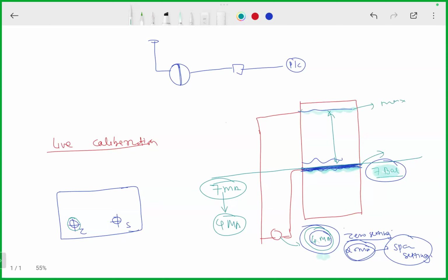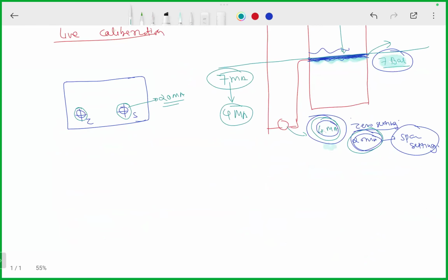So when water level is at the highest point, at that time the output signal should be 20 milliamp. If it is not 20 milliamp, it is something else, for example 16 or maybe 18 or maybe 15, so what you are going to do? You are going to adjust the span setting in such a way that output signal at highest water level is 20 milliamp. That is called your span and zero calibration.